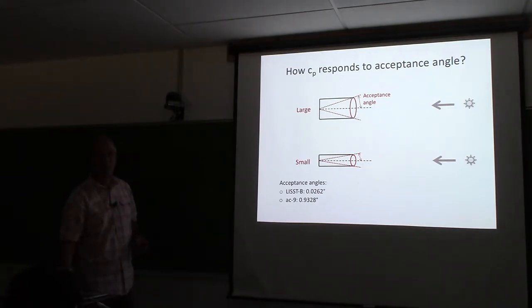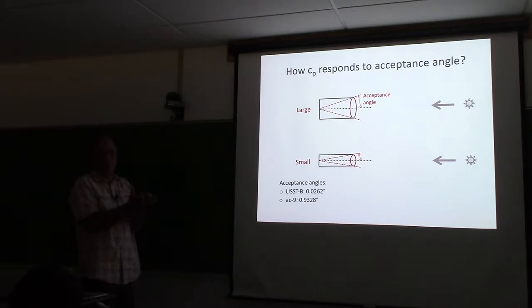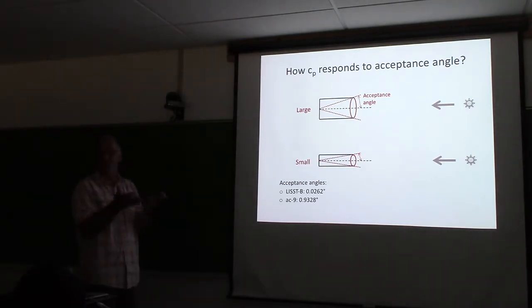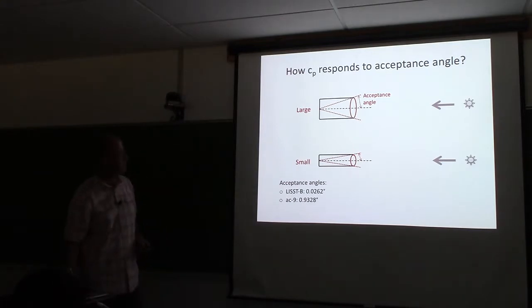Why would you use a more generous acceptance angle? It's because it's an easier measurement to make - less prone to getting affected by fouling and other things. So there are good reasons to have that more generous acceptance angle.